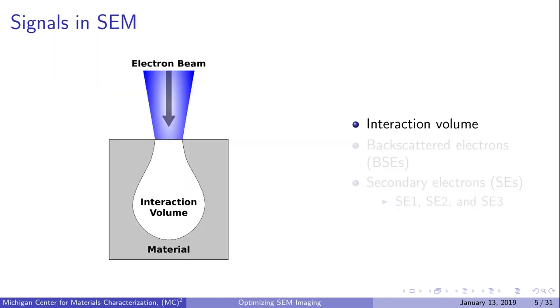When the electron beam hits the sample, it interacts with some of the atoms there to generate different types of electrons and x-rays. The volume that generates these electrons and x-rays is called the interaction volume. The size and shape of the interaction volume can vary depending on the sample composition, surface topography, and imaging parameters. While the interaction volume generates x-rays and electrons, we'll focus on the electrons in this lesson.